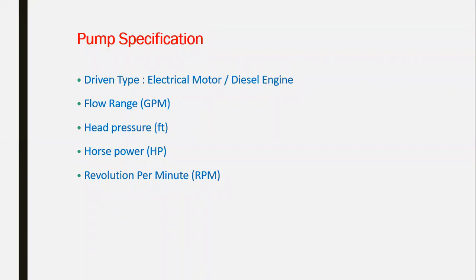What devices would be tested here within NFPA 25? We will start first with the pump. As we studied last time under NFPA 20 regarding the fire pump, there is a classification and type of the pump. It is different, either split case, vertical turbine, or end suction, etc. This is the pump. Another definition and category is the driven type, either electrical or diesel engine, the flow in GPM, gallons per minute, the head pressure in feet or bar, the horsepower, and revolutions per minute, the RPM, which is the speed of the motor.